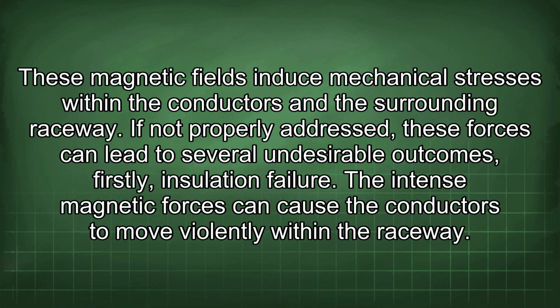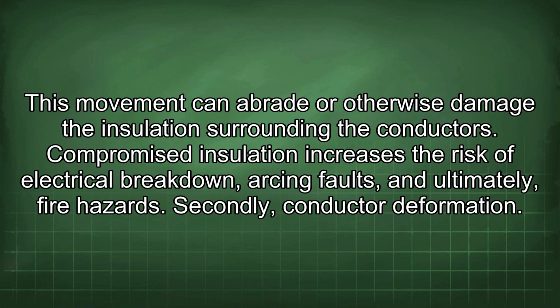These magnetic fields induce mechanical stresses within the conductors and the surrounding raceway. If not properly addressed, these forces can lead to several undesirable outcomes. Firstly, insulation failure. The intense magnetic forces can cause the conductors to move violently within the raceway. This movement can abrade or otherwise damage the insulation surrounding the conductors. Compromised insulation increases the risk of electrical breakdown, arcing faults, and ultimately, fire hazards.